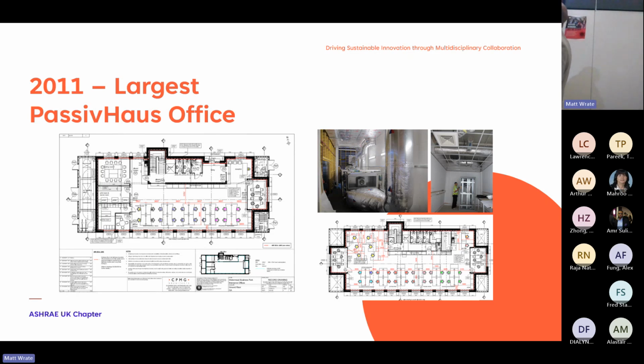One of the best things we had, really simple but it just worked because of the floor plan, was using the server room as the return air path. The ground floor plan's on the left, with the server room centrally located between the two meeting rooms. That gave us a return air path for all the air to come back from the main central office, picking up beneficial heat from the server room before it goes back onto the air handling unit to have that heat recovered and put back into the occupied spaces of the building.